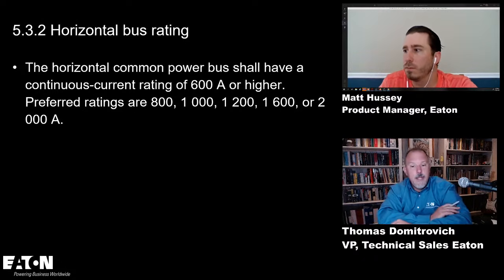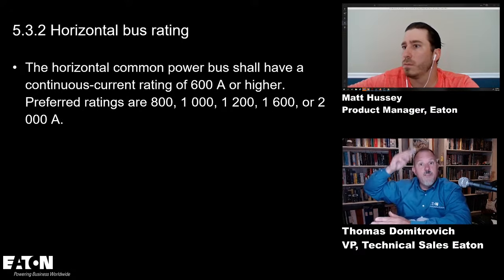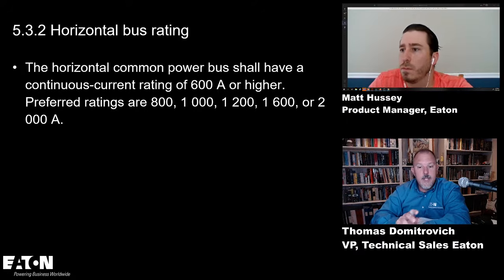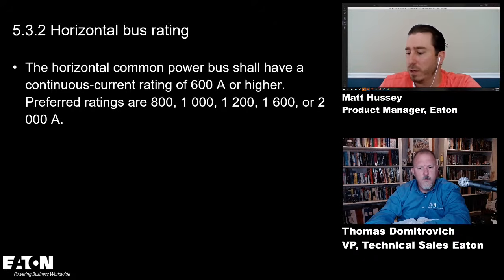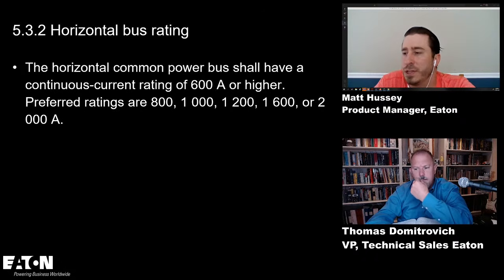That's right. Excellent. The horizontal bus rating, that's the common power bus that goes across the top when you have more than one vertical section. 600 amps or higher. Preferred ratings are 800, 1,000, 1,200, 1,600, or 2,000. What do they mean by preferred ratings? That's out of the standard. It's probably like nominal rating increments that are referenced there. Kind of like circuit breakers, where you have a typical increment from one range to the next. And the largest amp rating on a horizontal bus, at least what we make, is 3,200 amps. I'm not sure if there's another manufacturer that has something larger than that.